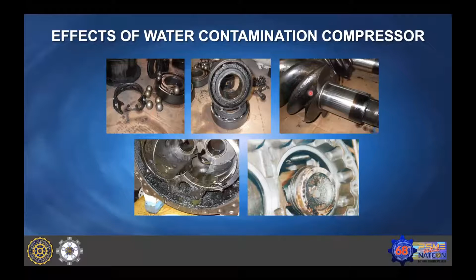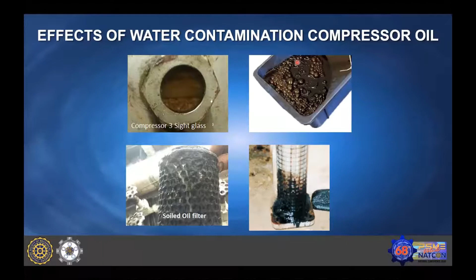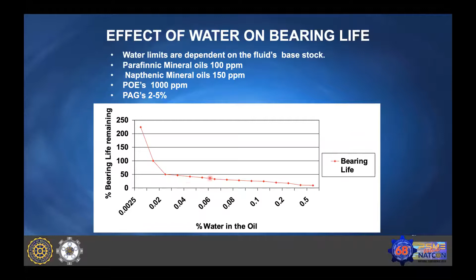These are some photographs of damage which has occurred to the compressor due to water getting into the system. You can see water accumulated in the oil sight glass, how the water shows when the oil is drained, and how these filters are choked with oil and sludge. The main effect of water is on the bearing life of the compressor. As the quantity of water increases in the oil, bearing life decreases tremendously.